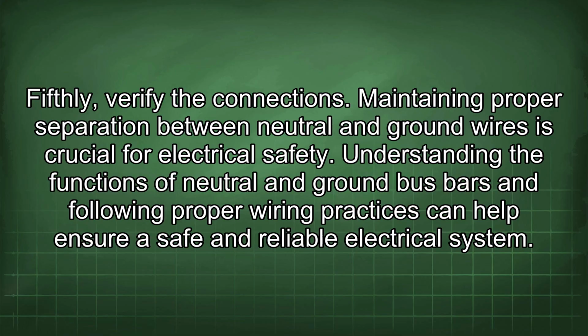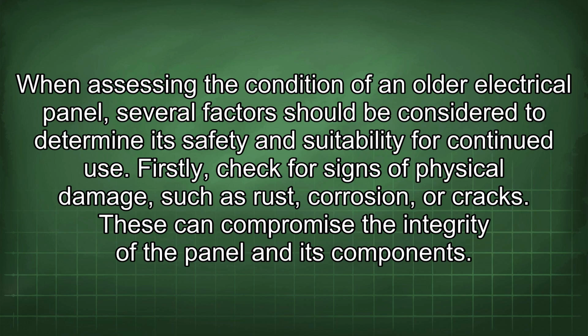Understanding the functions of neutral and ground bus bars and following proper wiring practices can help ensure a safe and reliable electrical system. When assessing the condition of an older electrical panel, several factors should be considered to determine its safety and suitability for continued use. Firstly, check for signs of physical damage, such as rust, corrosion, or cracks. These can compromise the integrity of the panel and its components.